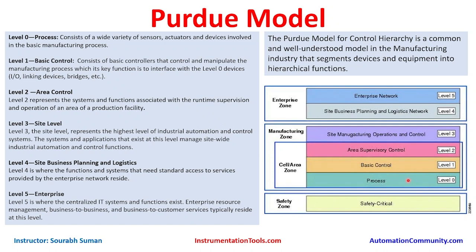Level 1 is the basic control level, consisting of basic controllers that control and manipulate the manufacturing process. We're talking about controllers and IO cards at this level, whose key function is to interface with level 0 devices. The basic control is directly connected to the process — cables from level 0 terminate at the IO level, or if wireless, devices communicate via Wi-Fi. In DCS or PLC systems, DI/DO and AI/AO cables connect to the basic control.